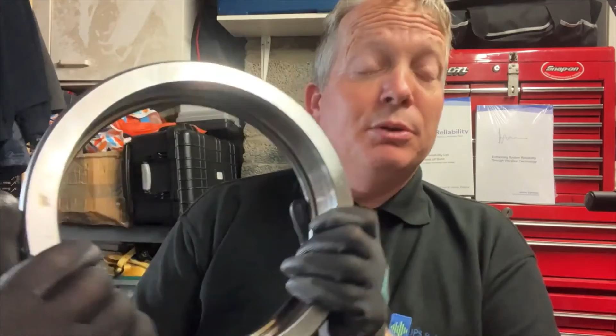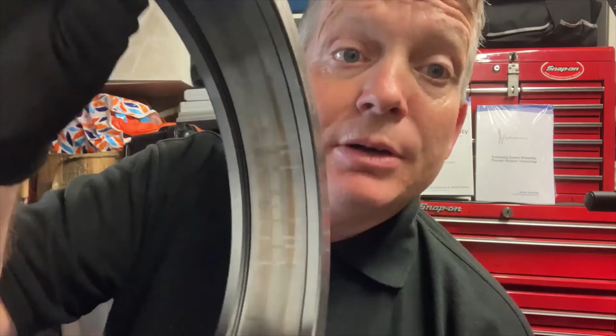Oof, there, see, nothing. Now if I flip it 180, so this is going to be the top of the motor. If we flip it 180 here, there we go. So there you can see false brinelling marks. Now you can see that there's like two groups of patches. So that's the two rolling elements which should have been in the bottom of the bearing, sat there getting that micro movement. But you can see the rotor has moved very slightly for the elements to move there to give you different indents. So that's the bearing.